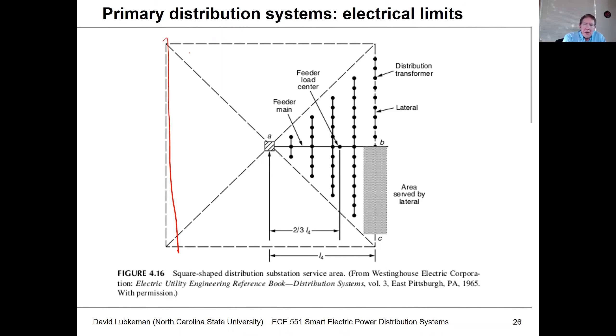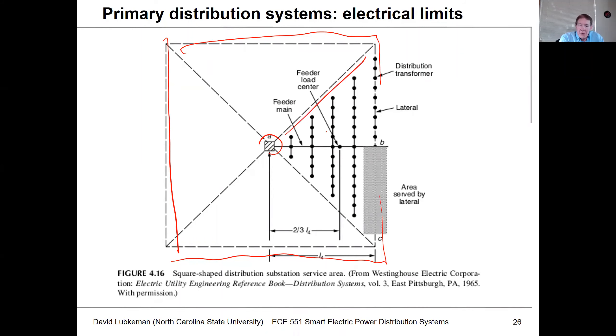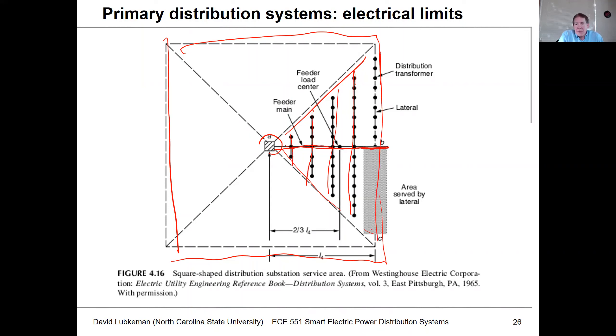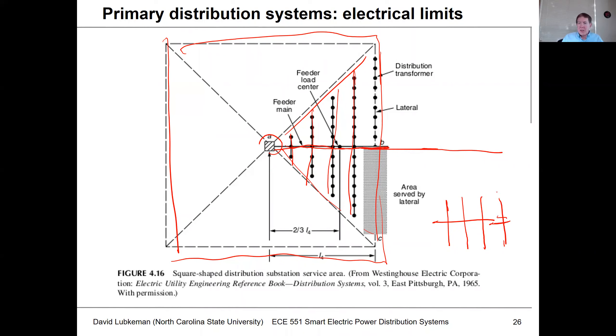From an old Westinghouse design manual: if you had a square area that you needed to supply service to, you would maybe start by putting a substation in the middle and breaking up into four different triangular-shaped areas. Then you'd have a main feeder coming out of the substation, and off this main feeder you'd have laterals, assuming that the load is going to be uniformly distributed. Another topology would be to assume that instead of having a linearly increasing load along the feeder, it's more uniformly distributed.